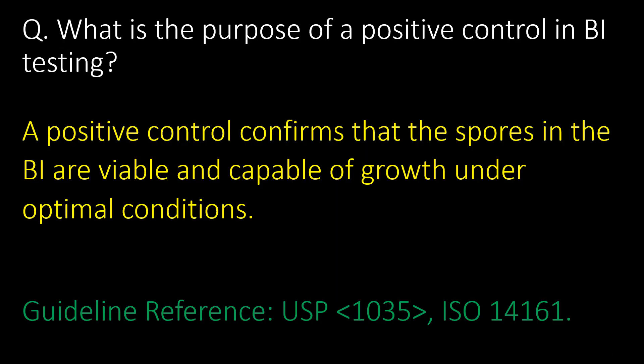What is the purpose of a positive control in biological indicator testing? A positive control confirms that the spores in the biological indicator are viable and capable of growth under optimal conditions. Reference guidelines: USP chapter 1035 and ISO 14161.